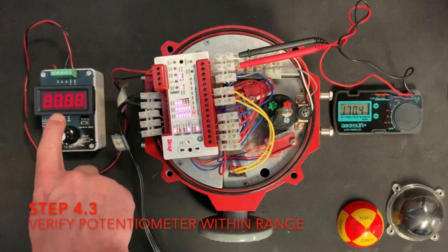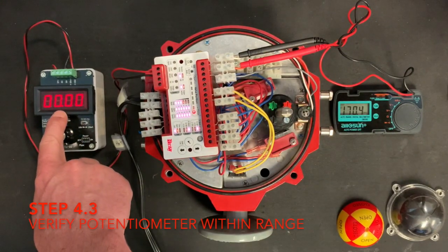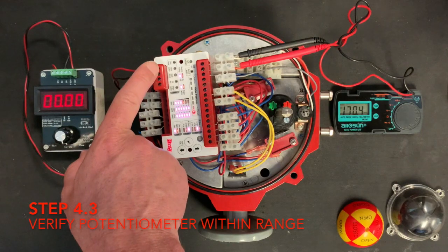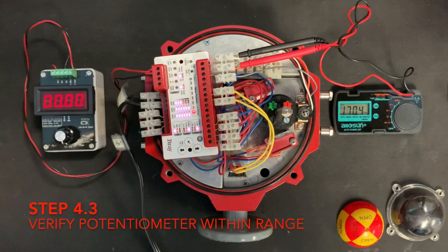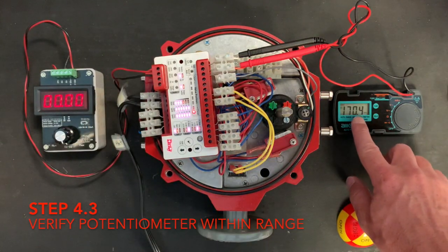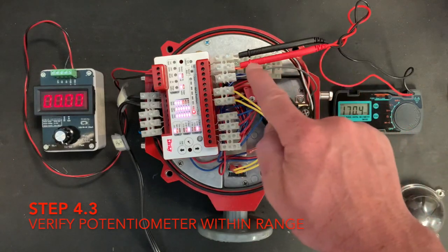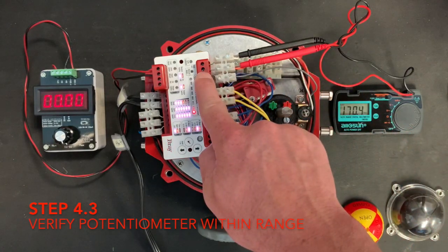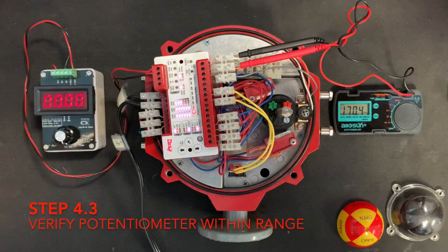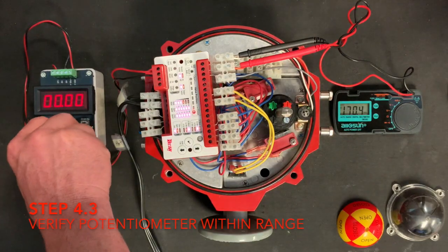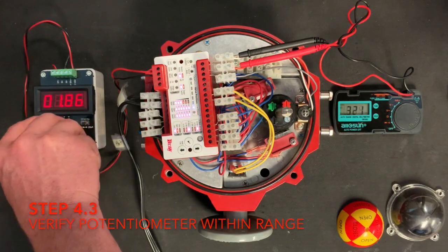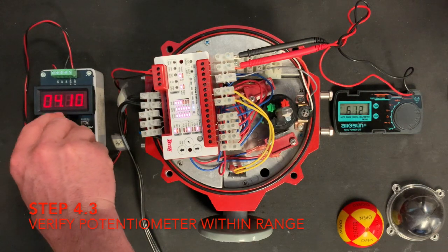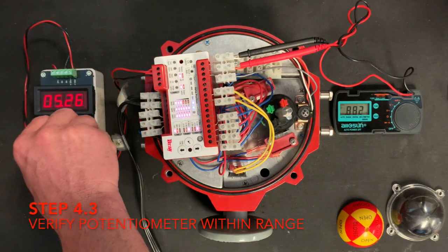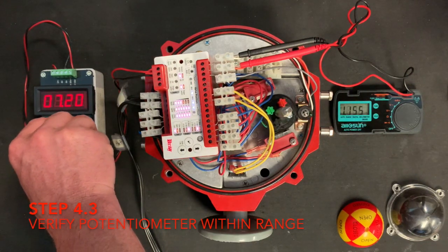Electrically command the actuator full open and close to verify proper valve position and recheck potentiometer VDC measurements to the specifications below using command inputs. If position and potentiometer measurements are good, then the calibration is complete. Otherwise, return to step 1 or contact Bray.